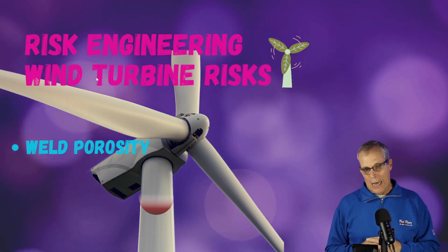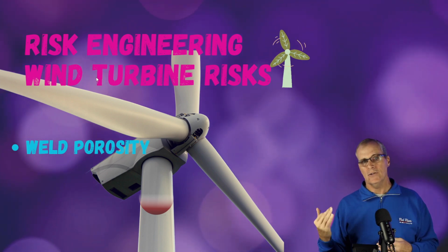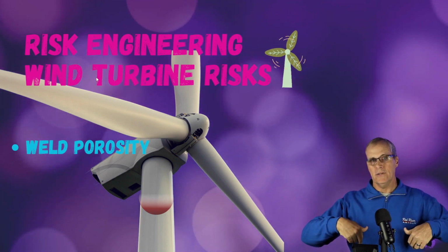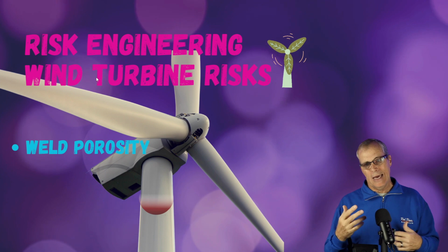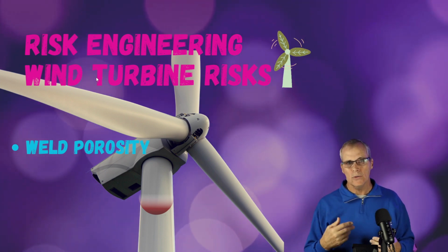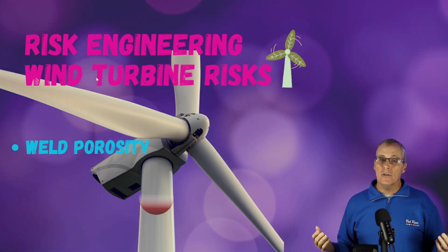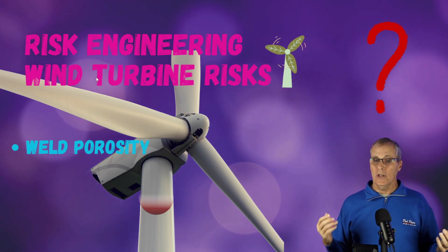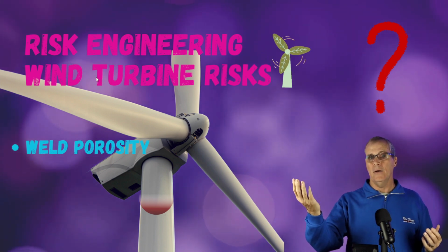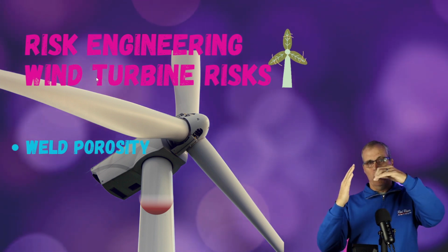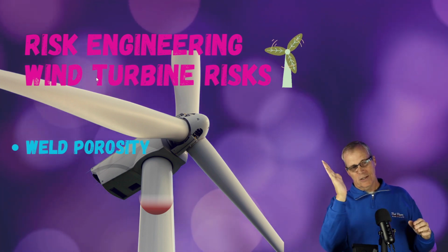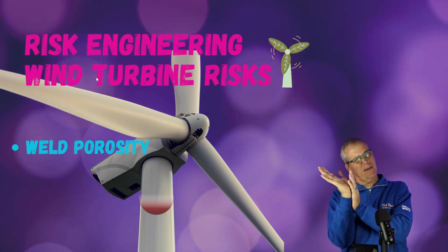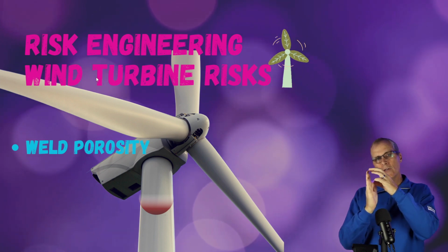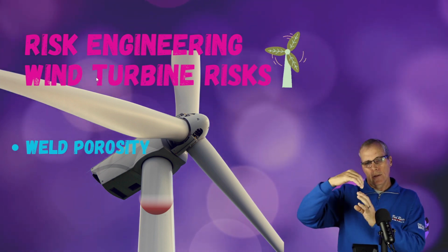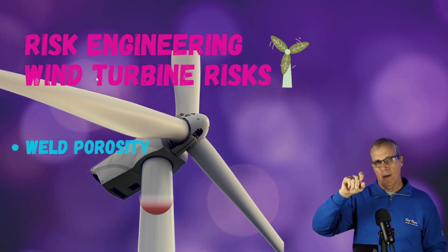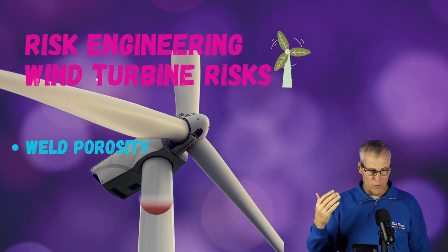So how does oil get on the outside of the tower if it all ran down the inside? And if it's on the outside, why is it only at these welds? Those were some of the questions we had. It was on the upwind side that we saw the oil leaking out—the side that got bent more. You can imagine the tension on that side opening it up a little and allowing the oil to flow out, if that's what was going on.